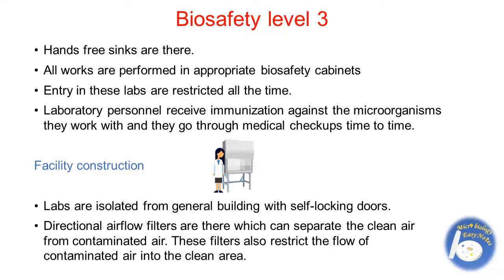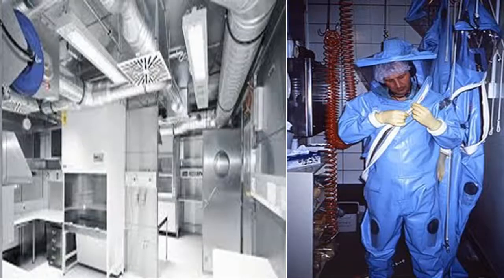Laboratory personnel receive immunizations against the microorganisms they work with and undergo medical check-ups regularly. Labs are isolated from the general building with self-locking doors. Directional airflow filters are installed which can separate clean air from contaminated air and restrict the flow of contaminated air into clean areas.